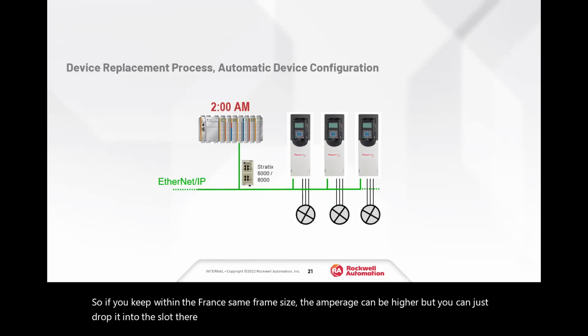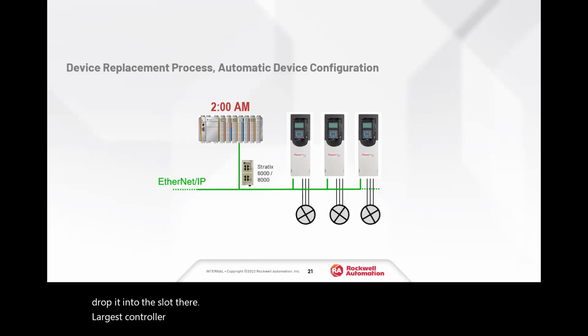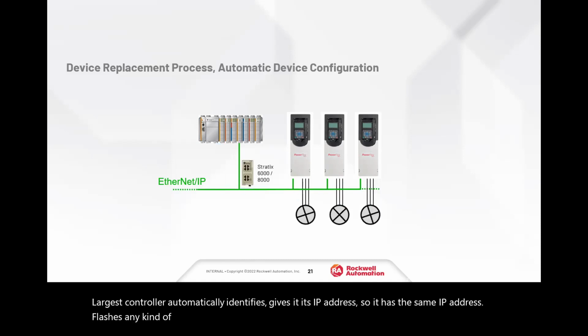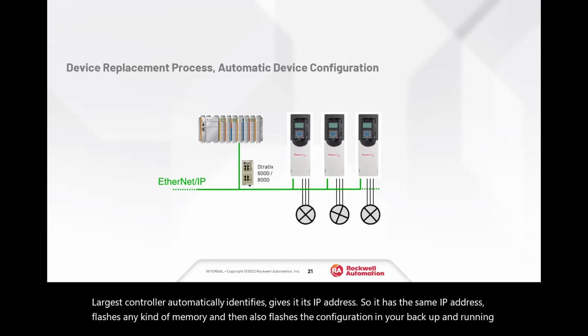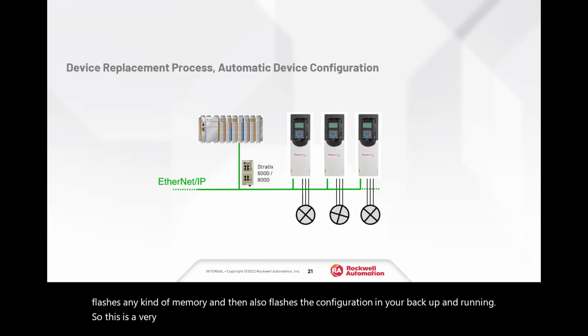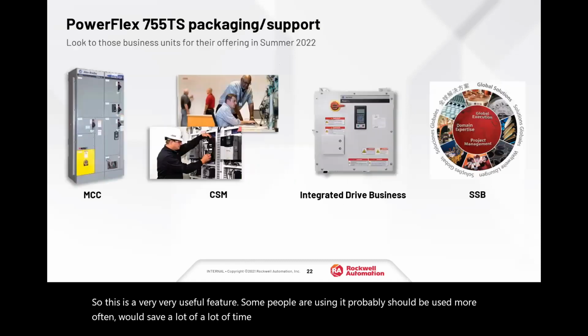The Logix controller automatically identifies it, gives it its IP address, so it has the same IP address, flashes any kind of memory, and then also flashes the configuration and you're back up and running. So this is a very, very useful feature. Some people are using it, but it probably should be used more often, as it would save a lot of downtime.